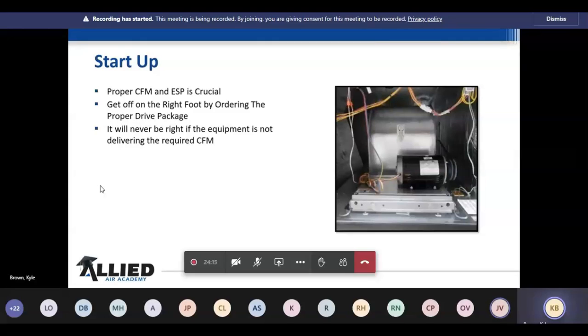You'll also hear me say a lot about proper CFM and external static pressure. Get off on the right foot by ordering the right drive package, and the unit will deliver CFM. So let's talk about this for a few minutes. We have two different segments. We have the emergency replacement segment, where you have a unit sitting in the warehouse and this bar, restaurant, or hospital goes down. You take that unit, you throw it on the roof, and we're going to get them up and going.